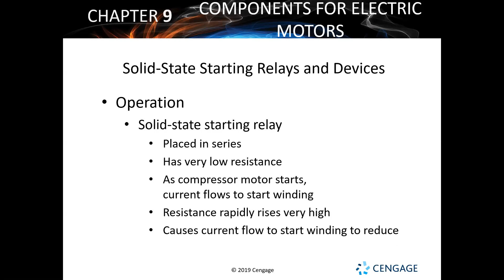Again, super easy to troubleshoot. The biggest thing you're going to be doing is using an ohm meter, checking for resistance. If it's supposed to be open, it should show OL on your meter. For a normally closed one, it should be close to zero, very low resistance across that relay.